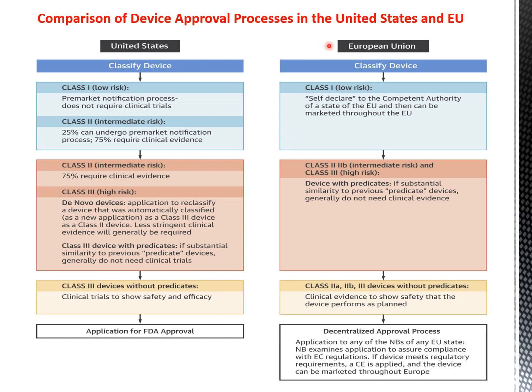Now coming to the European Union, it classifies as low risk, Class 1, Class 2A and 2B as intermediate and Class 3 as high risk. For Class 1, self-declare to the competent authority of a state of the EU and then you can market throughout the EU. For Class 2 devices and Class 3 devices with the predicates, if substantial similarity is seen, generally these devices do not require any clinical evidence.